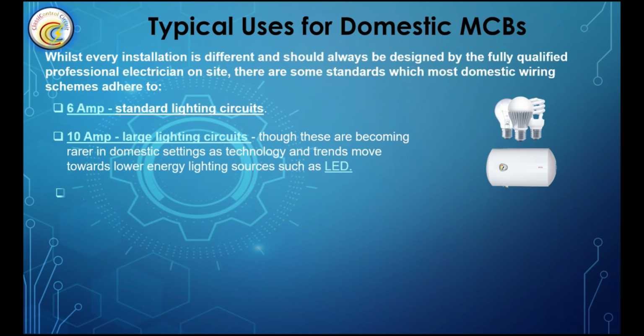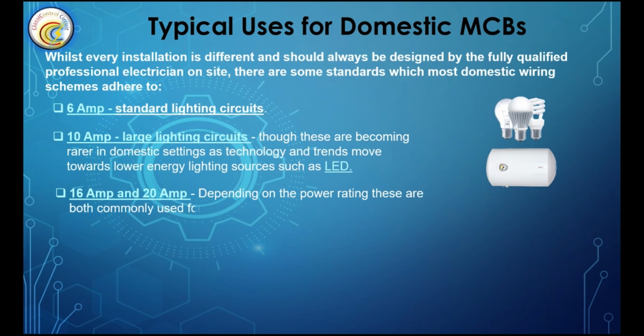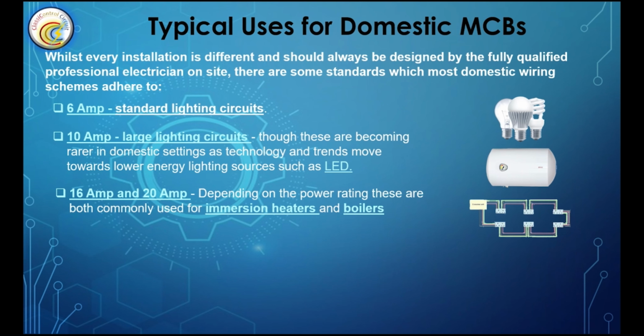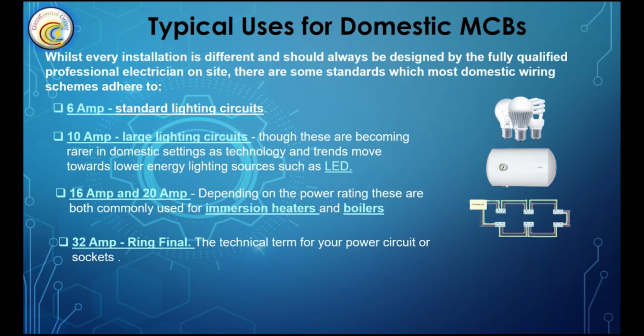16 amp and 20 amp. Depending on the power rating, these are both commonly used for immersion heaters and boilers. 32 amp: ring final, the technical term for your power circuit or sockets. 40 amp: cookers, electric hobs, small showers.